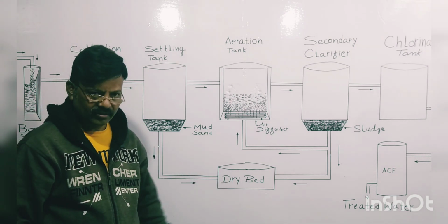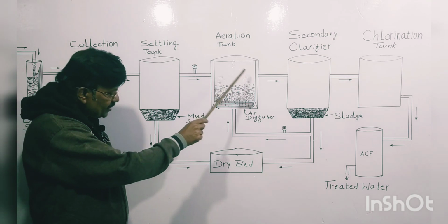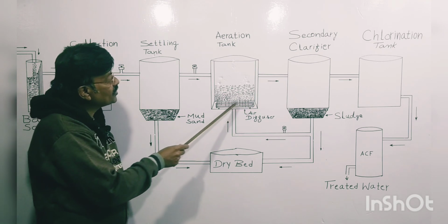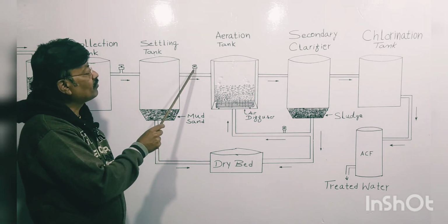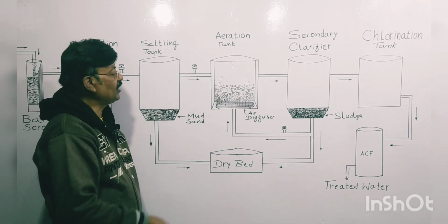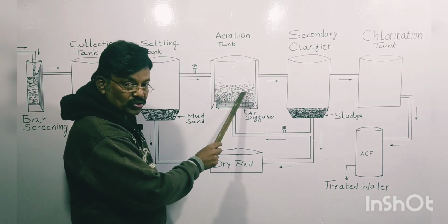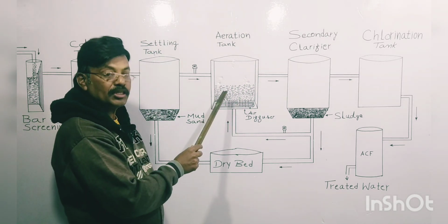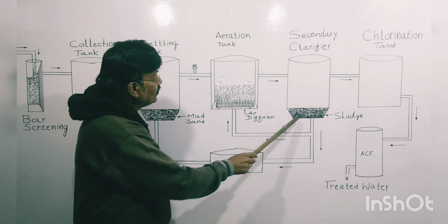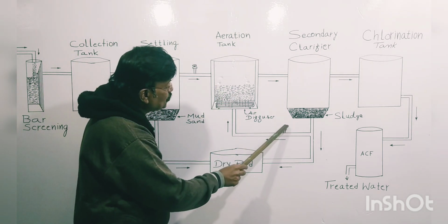As per the design of the aeration tank, that is the size of the aeration tank, and the air we are getting from these diffusers, the inlet flow rate of the sewage should be adjusted accordingly. Similarly, as per the food available in the aeration tank, that is organic matter, nothing but BOD, the amount of return activated sludge to the aeration tank should be adjusted.